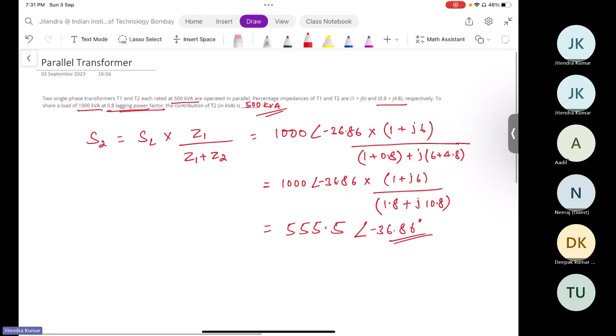Without pen and paper, you would have made a miserable mistake, right? So it's very important to go ahead with the given expression, the conventional formula, to avoid the mistake. Why does this happen? Because you have a certain power factor, and that power factor plays a very important role in how much power is supplied from which transformer and in what ratio. So do not get influenced just by seeing that 1000 kVA and 500 kVA are operated in parallel.